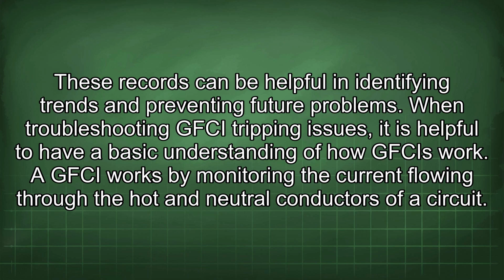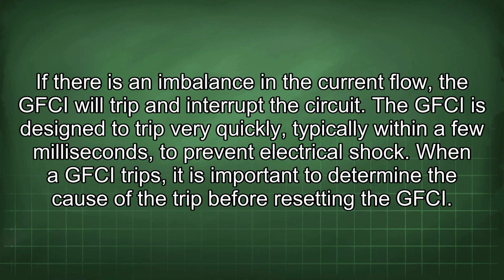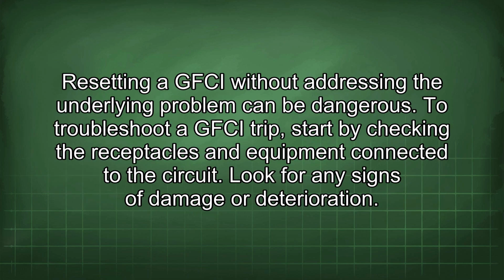When troubleshooting GFCI tripping issues, it is helpful to have a basic understanding of how GFCIs work. A GFCI works by monitoring the current flowing through the hot and neutral conductors of a circuit. If there is an imbalance in the current flow, the GFCI will trip and interrupt the circuit. The GFCI is designed to trip very quickly, typically within a few milliseconds, to prevent electrical shock. When a GFCI trips, it is important to determine the cause of the trip before resetting the GFCI. Resetting a GFCI without addressing the underlying problem can be dangerous.